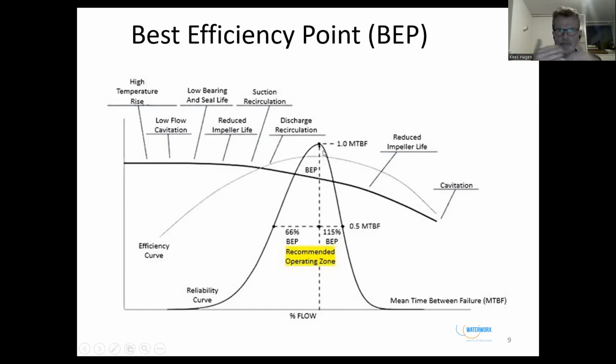Well, there are always changing situations in which pumps are running, changing suction pressures, changing discharge pressures. So it won't be one duty point on which a pump is working, but you always want to try to select a pump which is running in a certain recommended operation zone in which you have the maximum efficiency which is possible for this pump.